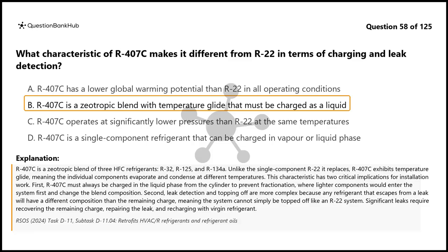Second, leak detection and topping off are more complex because any refrigerant that escapes from a leak will have a different composition than the remaining charge, meaning the system cannot simply be topped off like an R22 system. Significant leaks require recovering the remaining charge, repairing the leak, and recharging with virgin refrigerant.